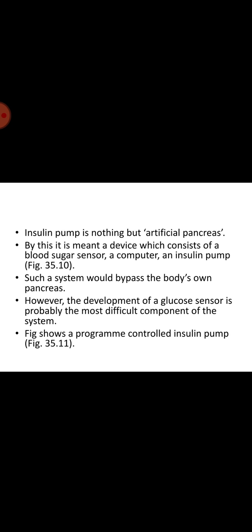The device can deliver insulin in two ways. One is a fixed program unit with a preset 24-hour rate per time profile, and the other is the demand program unit with which a basal rate is pre-selected and a supplementary dose is triggered at meal times.